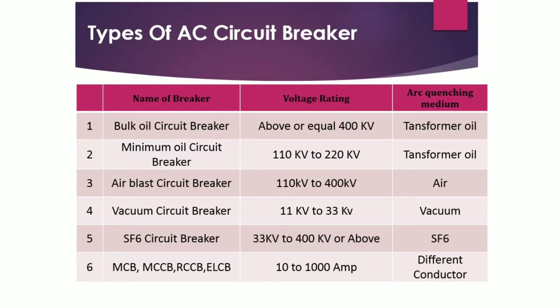Third is the air blast circuit breaker, with a voltage level of 110 kV to 400 kV, using air as the arc-quenching medium. Fourth is the vacuum circuit breaker (VCB), with a voltage rating of 11 kV to 33 kV, using vacuum as the arc-quenching medium. Fifth is the SF6 circuit breaker, with a voltage rating of 33 kV to 400 kV or above, using SF6 gas as the arc-quenching medium.